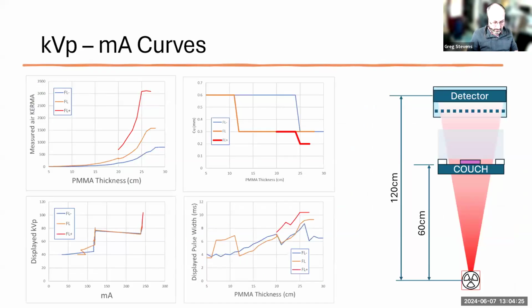So far, the most useful thing we've done is to measure the kV PMMA curves. What I'd like to draw your attention to is that the main parameter to cope with different thicknesses is the pulse width. You can see the pulse width, the bottom right-hand curve, is wiggling all over the place, whereas the rest of them don't really move that much. That's very different to the old systems.